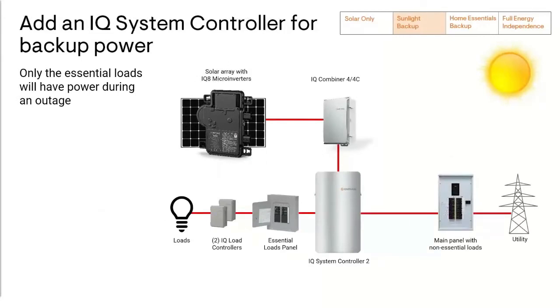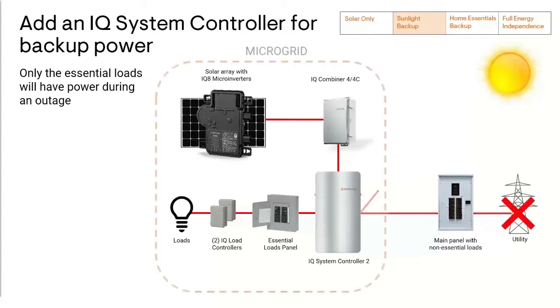Let's review a simple single-line diagram which illustrates how the system works. When the utility grid fails, the IQ system controller disconnects from the grid. If it is sunny, the microgrid is instantly formed by the IQ8 microinverters. The essential loads panel will have continuous power from the microgrid, and the circuits in the main panel will no longer have power. If the power outage occurs at night, the IQ8s will wake up when the sunshine hits the solar panels in the morning, and the microgrid will form. Then the system will power the essential loads. The load control feature will manage the loads early in the morning and late in the afternoon when the available solar power is low, so the customer doesn't experience a herky-jerky on-off experience.